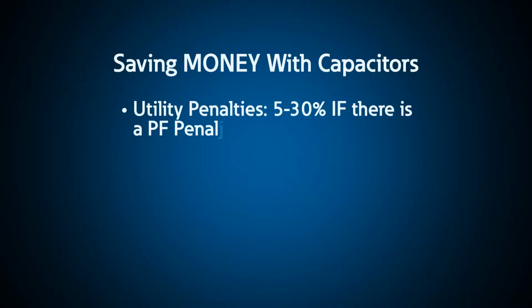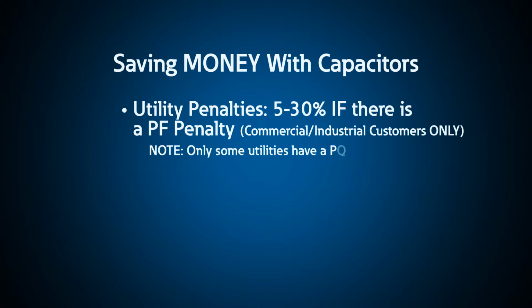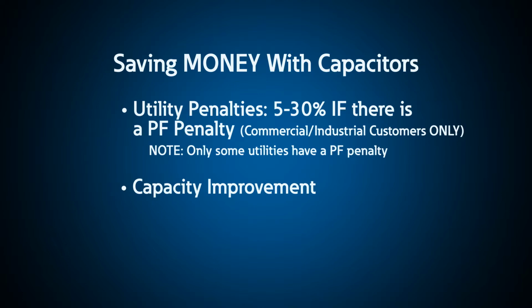Utility penalties, usually in the range of 5 to 30% of the total electrical bill. Capacity improvement, usually the benefit here is that if you install capacitors to improve your kVA capacity, you don't need to buy a new transformer or cables. Finally, I²R loss reduction can be achieved by installing capacitors near the load to reduce the current. The reality is, however, that power system losses are typically 1 to 4% or less.